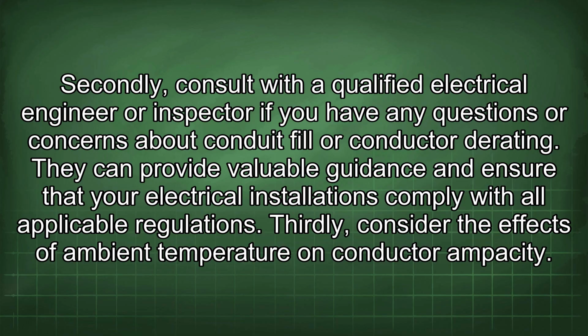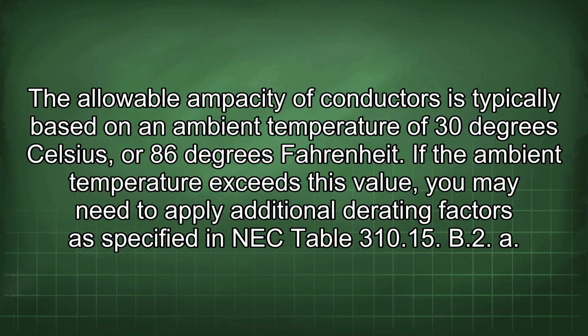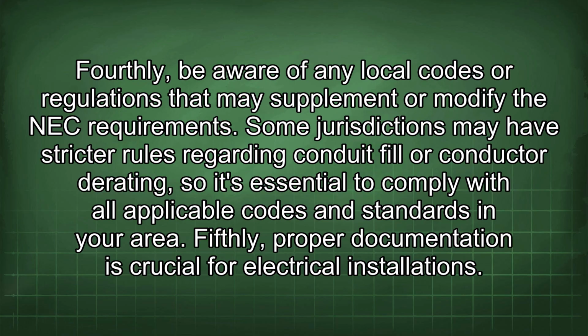Thirdly, consider the effects of ambient temperature on conductor ampacity. The allowable ampacity of conductors is typically based on an ambient temperature of 30 degrees Celsius or 86 degrees Fahrenheit. If the ambient temperature exceeds this value, you may need to apply additional derating factors as specified in NEC Table 310.15(B)(2). Fourthly, be aware of any local codes or regulations that may supplement or modify the NEC requirements. Some jurisdictions may have stricter rules regarding conduit fill or conductor derating, so it's essential to comply with all applicable codes and standards in your area.